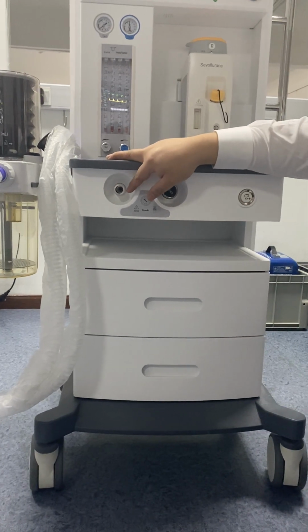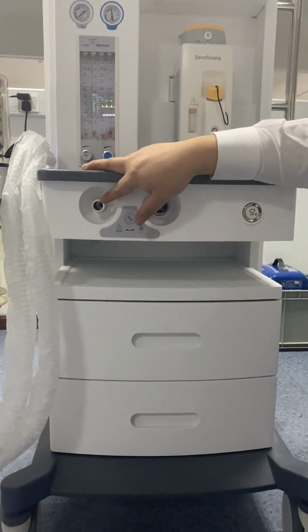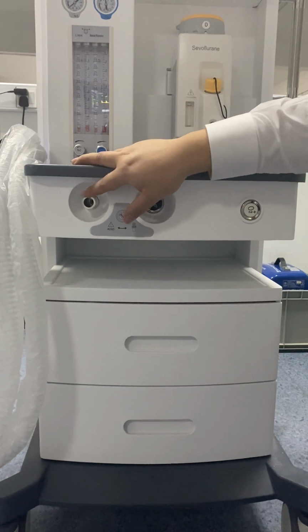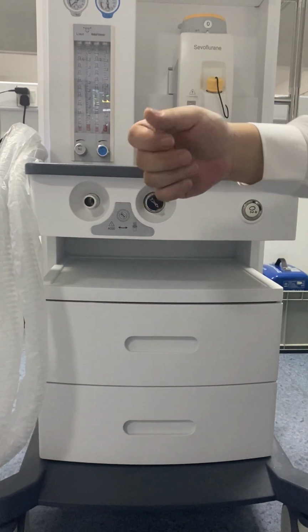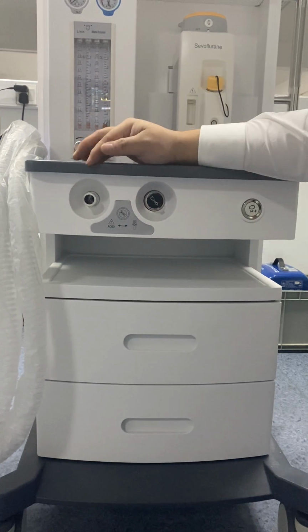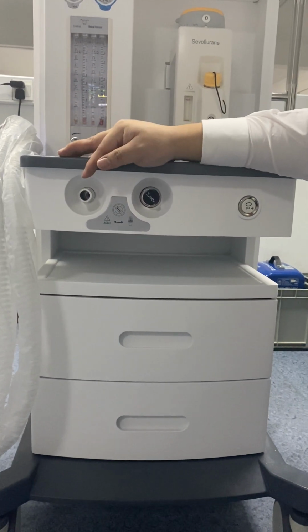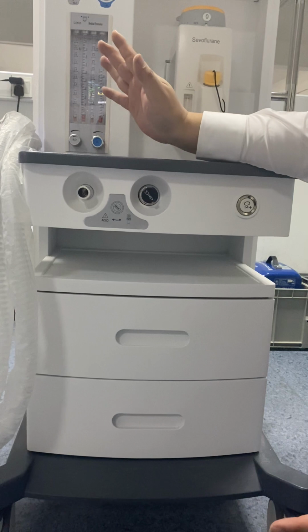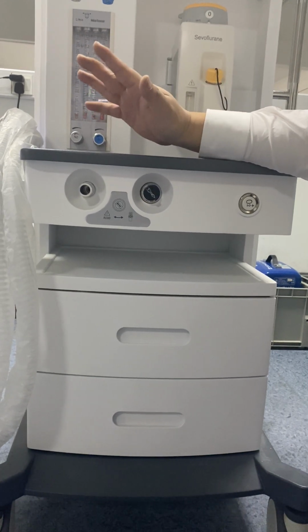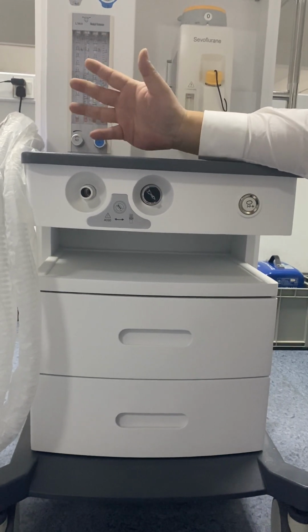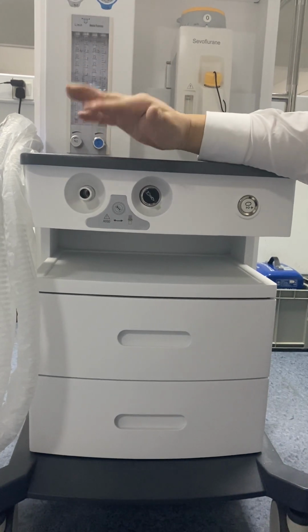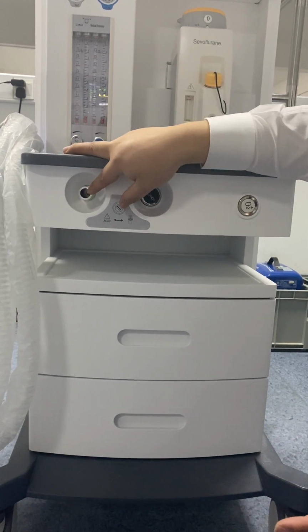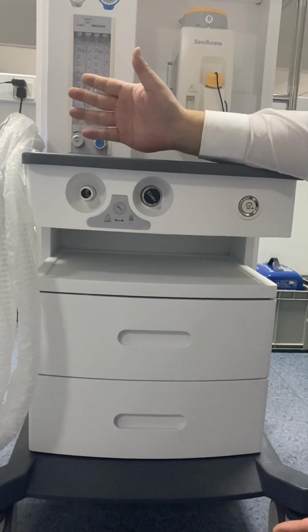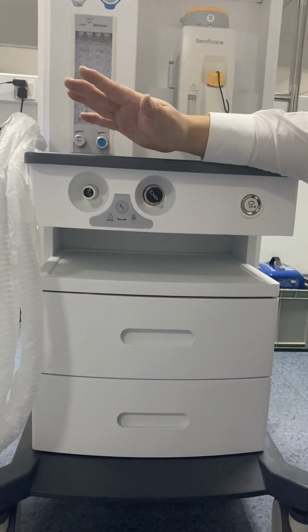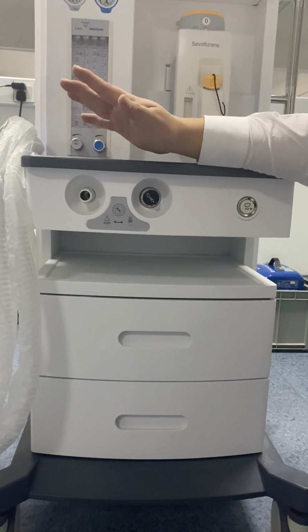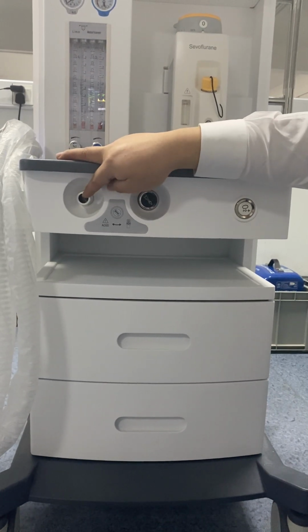And the third function is that only when we have the ACGO port can we do the open circuit operation. We connect the pipeline here and do the open circuit by pressing the bag. And the last function is also very important. We know our machine has a built-in battery, but in some emergency situations, the AC power fails and the battery also goes out. We can still use the ACGO port to give gas to the patient. At least we should ensure the patient is always alive and safe. So these are the 4 functions of the ACGO port.